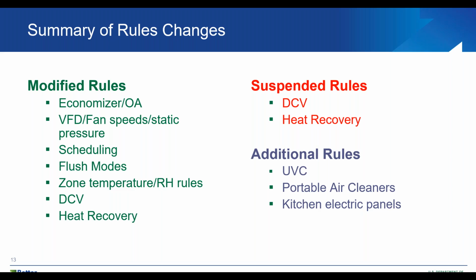They're actually doing the opposite, where beforehand you were running them for energy savings. Now you need to shut them off and suspend them because you're not as focused on the energy savings, but you're more focused on the health of the building. Then additional rules will also need to be created. Maybe there are additional systems that have been installed, like UVC, or you've added portable air cleaners or other equipment, and you need to make changes by adding additional rules and then paying attention to those under COVID-19 conditions.